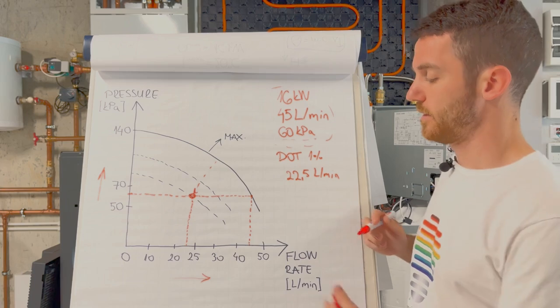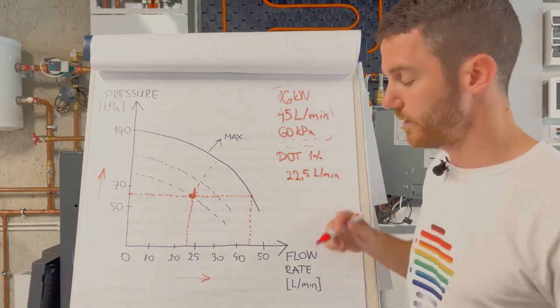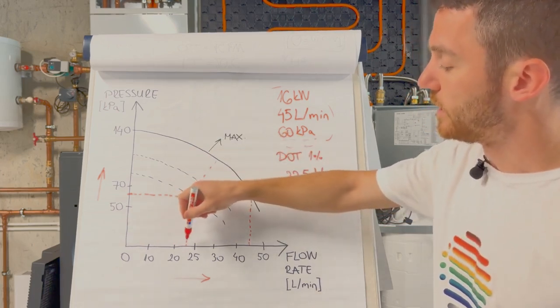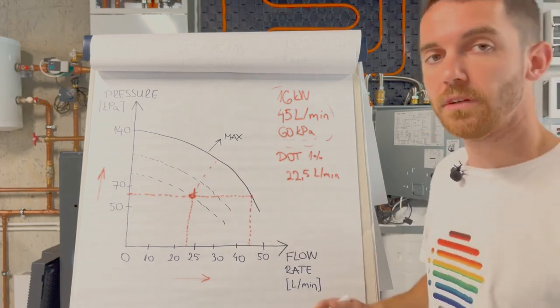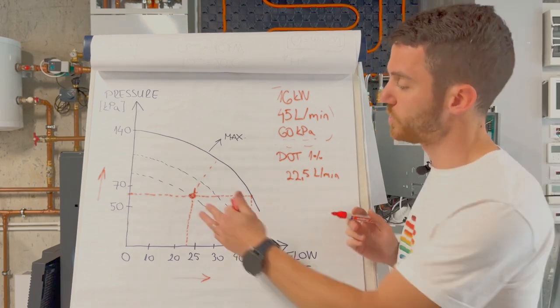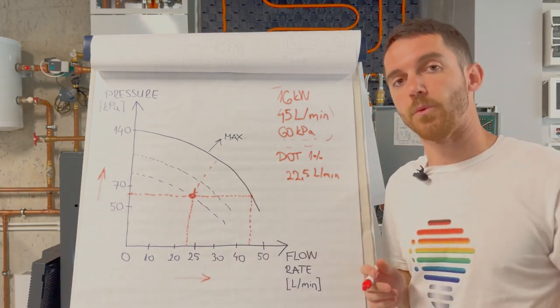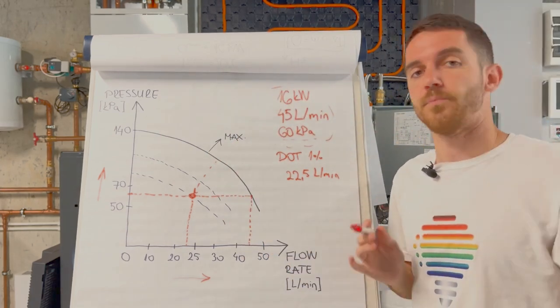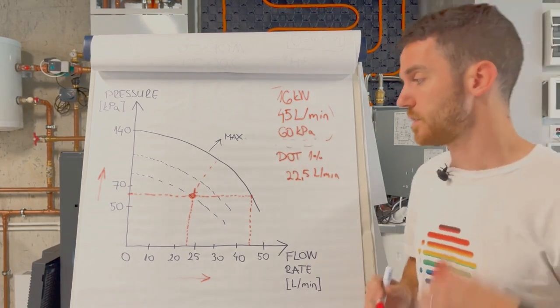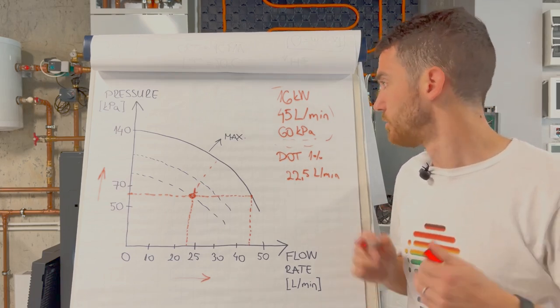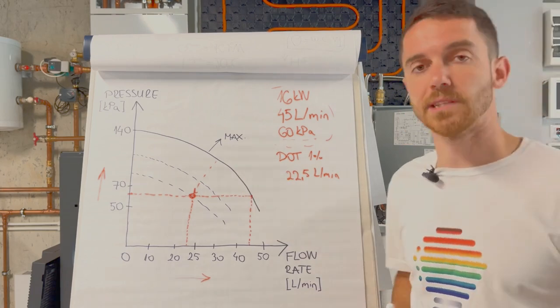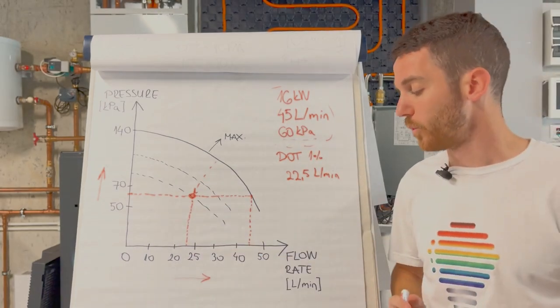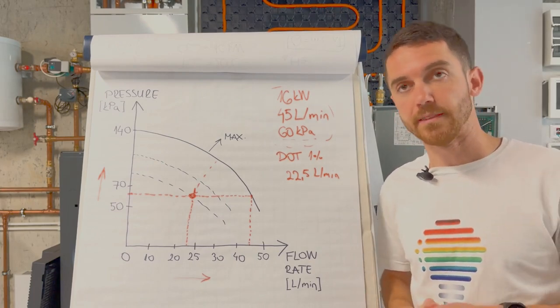Of course this is 16 kilowatts. The same pump is for 12 kilowatt, even for nine. So for this, let's say lower nominal flow rate around 20-25 liters per minute, you can go with lower curve and you will have really nominal working condition. You don't need to go on maximum curve. If you have a system which needs adoption on maximum curve, you can set up on Panasonic unit maximum curve. It means when your system needs maximum flow rate, maximum kilowatts, your pump will run on maximum. When it's not the case, your pump will modulate down whatever your flow rate is needed.